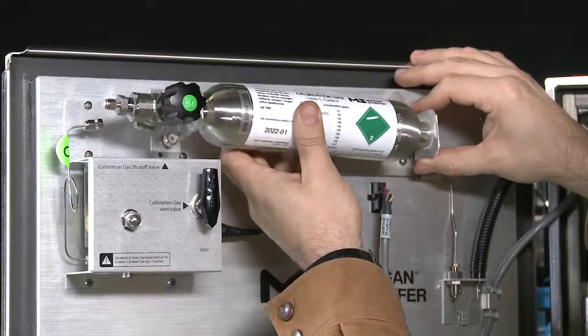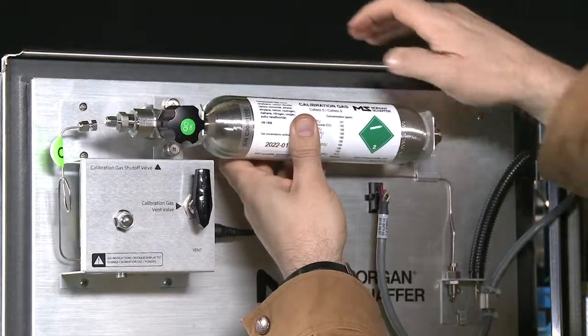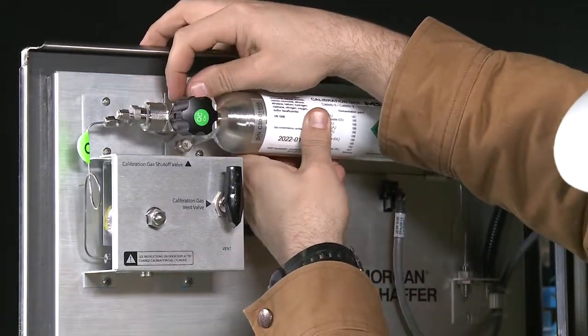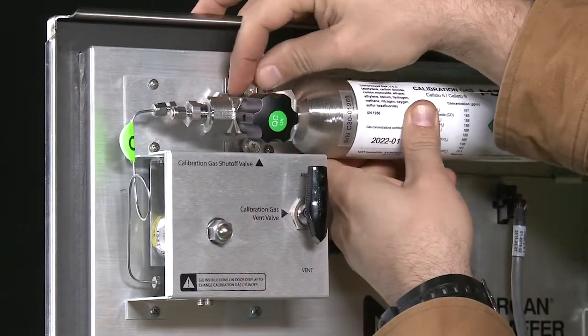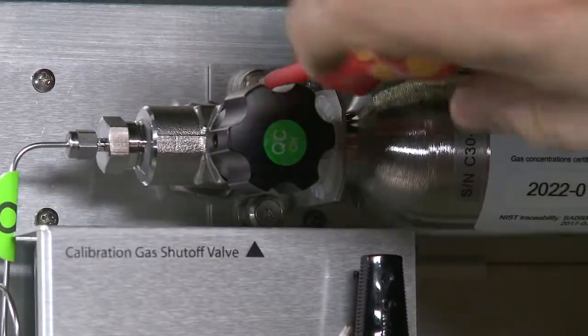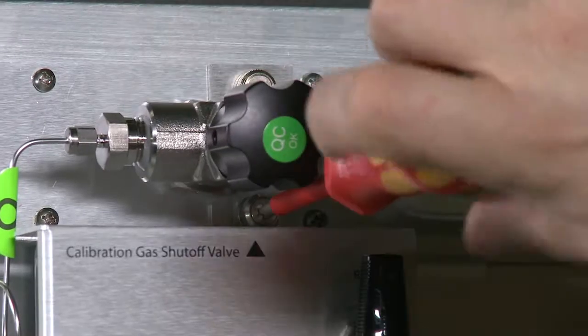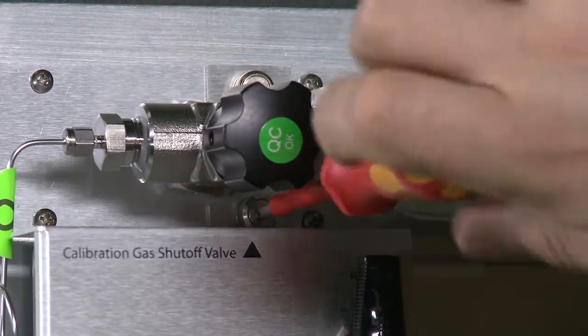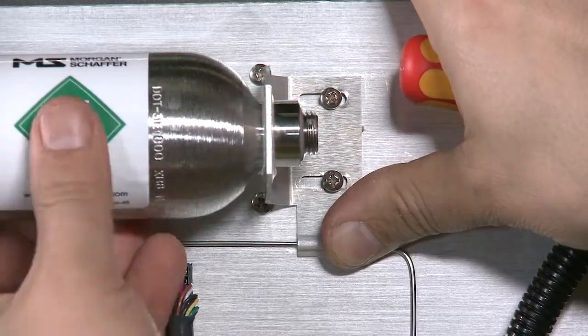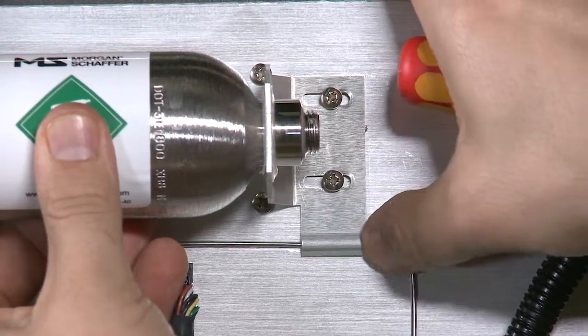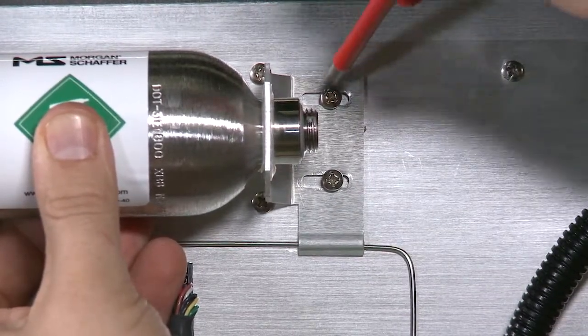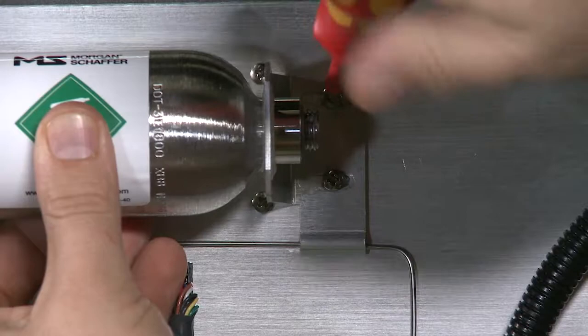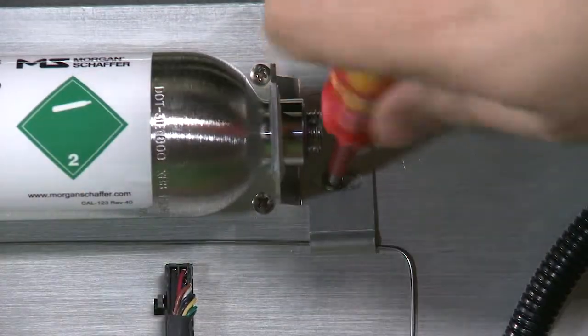Install the cylinder by inserting the bottom of it into the retainer first, then turning the 2 captive screws by hand and tightening using a Phillips No. 2 screwdriver. Adjust the cylinder retainer so that it holds the cylinder bottom properly. Then tighten the 2 screws using a Phillips No. 2 screwdriver.